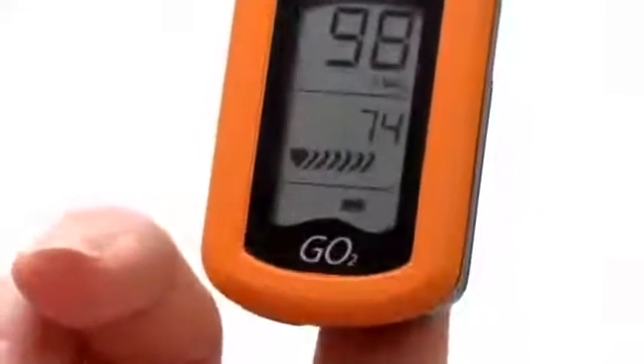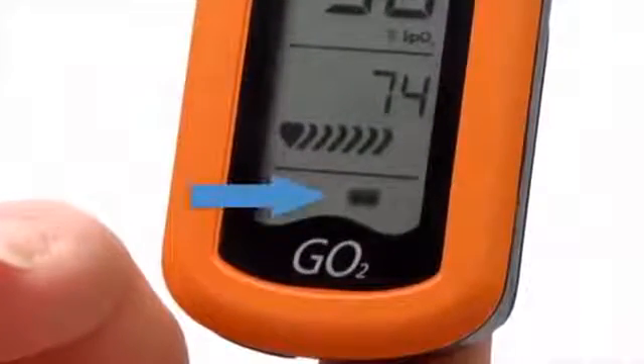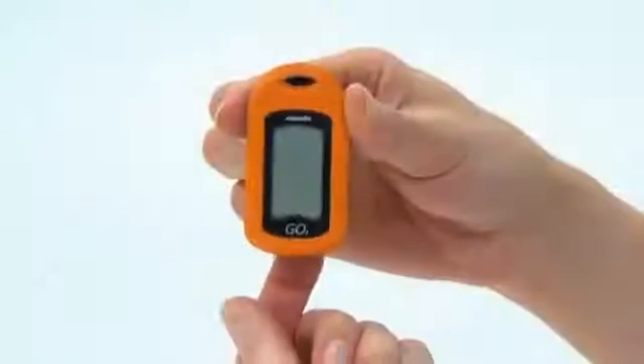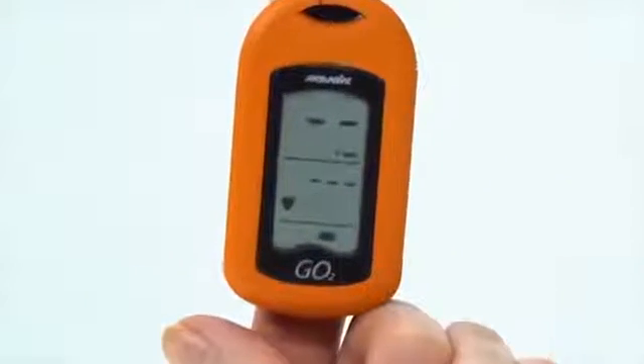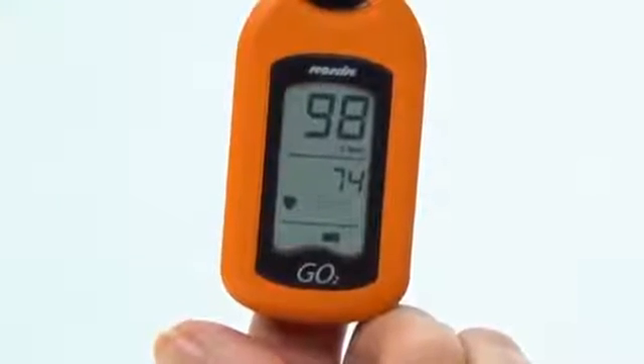You can see the remaining battery life and when a battery change is needed during use. The indicator will flash when the battery reaches a critical level. To use the GO² oximeter, just slide your finger into the opening in the oximeter until it touches the stop guide, with your palm up and the display facing up for easy viewing. The oximeter is hinged to gently hold the sensors on the top and bottom of your fingertip.